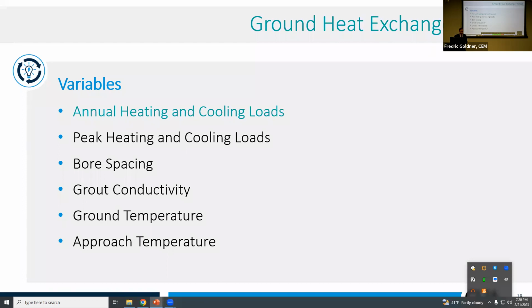Grout conductivity, 1.2 is pretty much the typical. Don't buy anything less than 1.0. But again, if your grout has a greater conductivity than the actual earth it's connected to, what are you doing? Ground temperature, we know that the average temperature around here is 53 degrees. The swing is minute, maybe dips down into the high 30s on a natural sort of occasion. This is a very good temperature for geothermal.